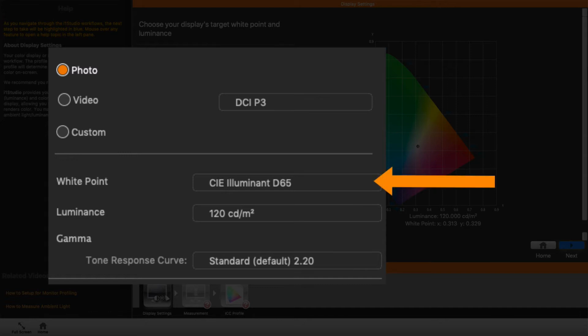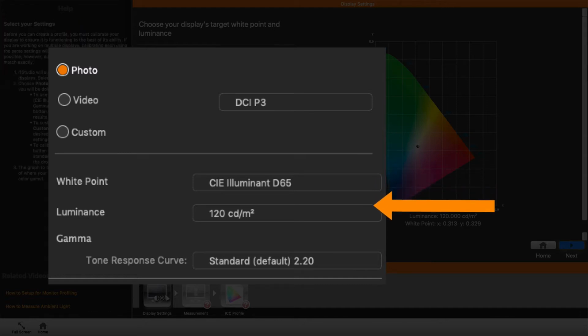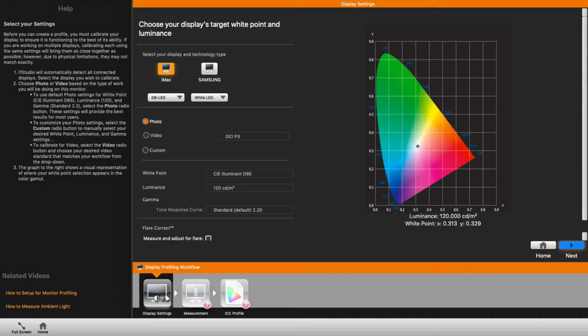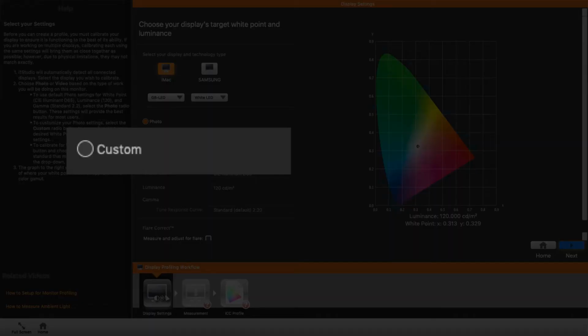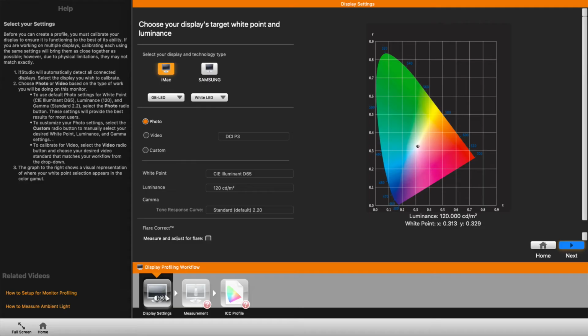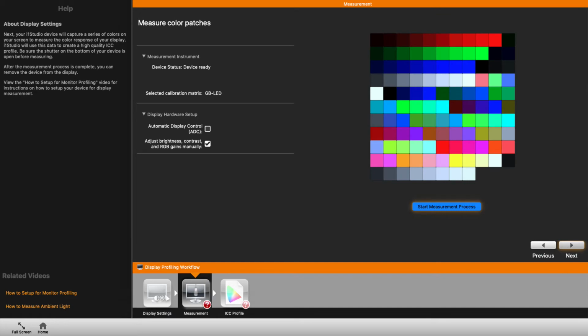The white point illuminant of D65, a luminance level of 120, and a gamma of 2.2. If these settings are not your default settings for your software, you can just use the custom settings and set them yourself. But notice, that's exactly what we said we were going to use when we started this whole process. The wizard steps you through the process, and it tells me that my device is ready.